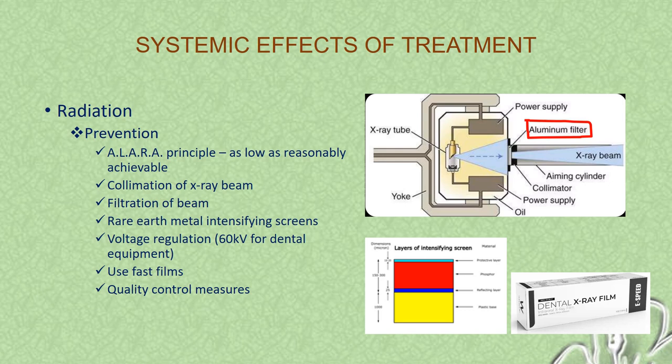To prevent radiation effects, we must follow the ALARA principle — as low as reasonably achievable. We can use collimation of the X-ray beam, filtration of the beam, and rare earth intensifying screens, which reduce the intensity of X radiation. Voltage regulation is 60 kV for dental equipment. Use of fast film is also helpful as fast films allow shorter exposure times. Quality control measures must be constantly enforced in premises with radiographic equipment.